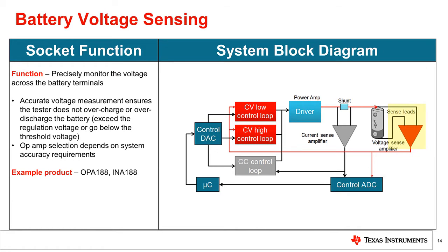You will need to consider your system needs and design goals when selecting for this socket. Remember that the unit will be monitoring your battery voltage, and its output will determine when the safety, regulation, and threshold protections kick in. Also consider that while most batteries may charge slowly, which might lead you to think very little bandwidth is needed in this socket, if your system needs to measure impedance via charge injection, you'll need high bandwidth in this socket to accurately measure the quick shifts in battery voltage that will arise from the injected current.